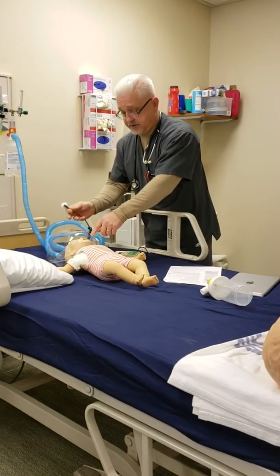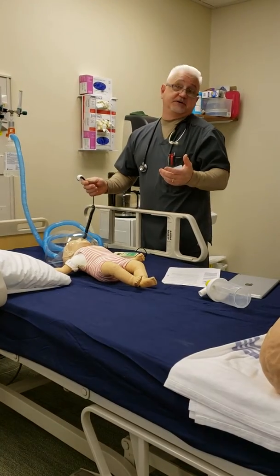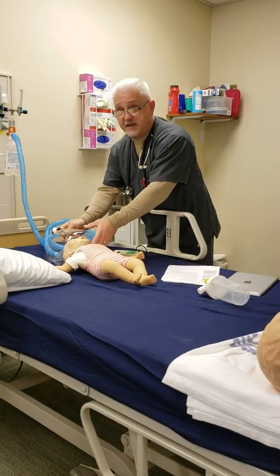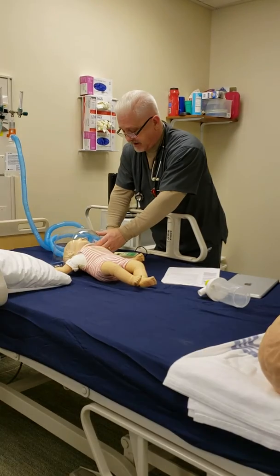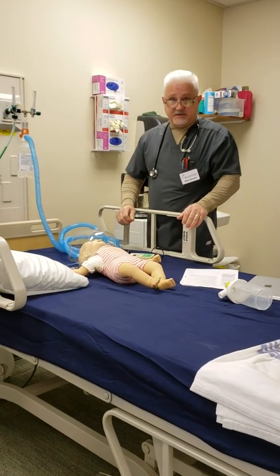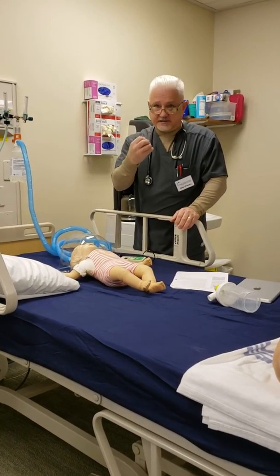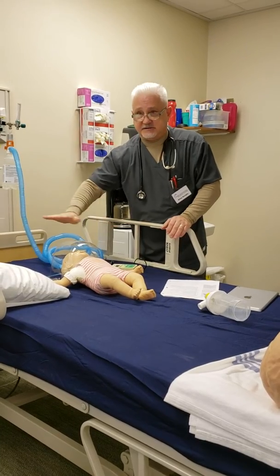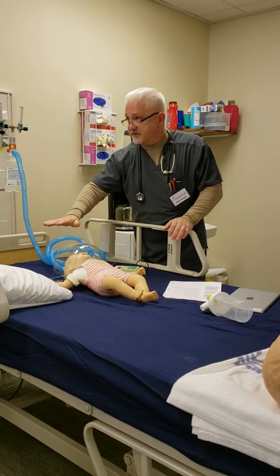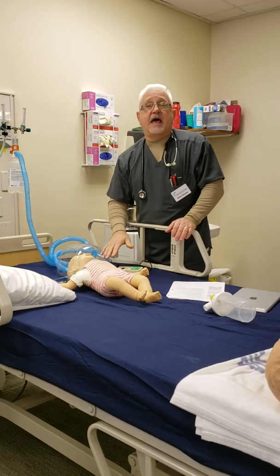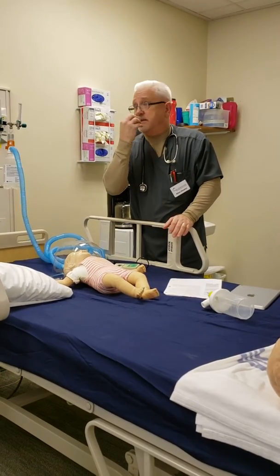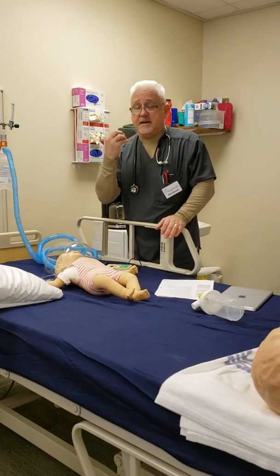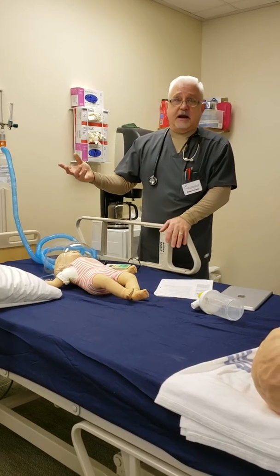What you're going to do is, normally your baby will not have their head straight up. They'll be turned to one side or the other. Wherever the baby's head is, you're going to put the O2 analyzer closest to the baby's nose or mouth. Not right on top, but close, because the gases are going to be stratified. It's going to be levels of different types of gases, and we want to analyze what's closest to where the baby's breathing. Okay? Remember, oxygen is more dense than air.